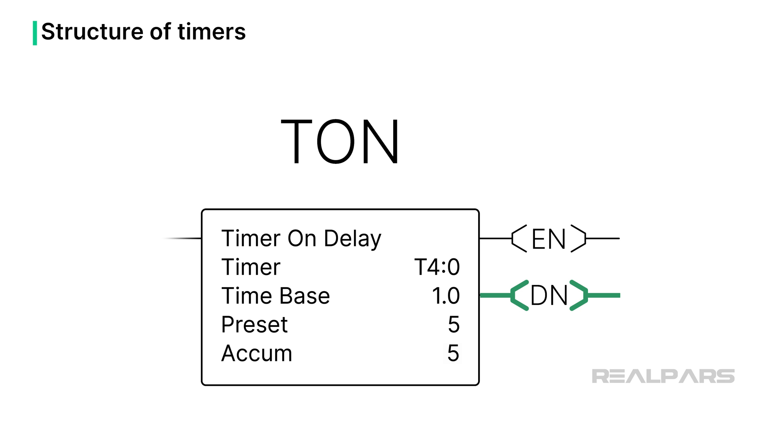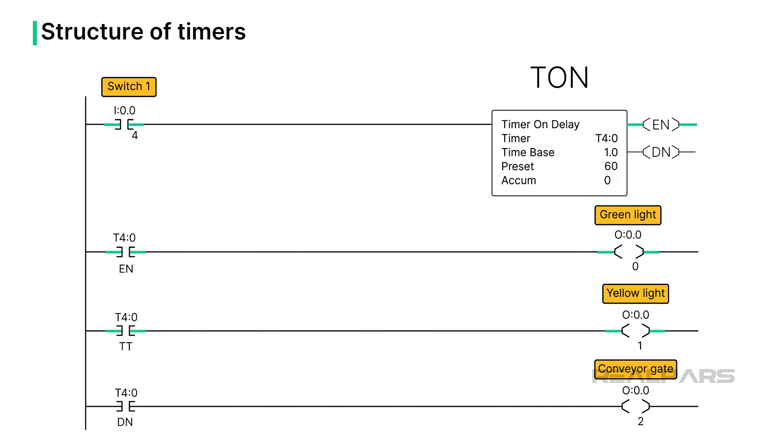During the time that the timer is enabled and timing up to the preset value, the enable, or EN bit, and timing, or TT bit, is set. These bits can be used in other rungs of the logic to allow downstream logic to execute.